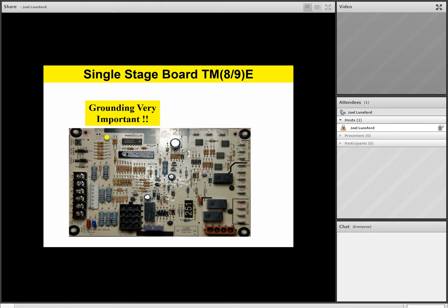You want to make sure you have a clean flame sensor. A lot of technicians have all different techniques of cleaning the flame sensor. We recommend you do not use sandcloth, but instead use something like stainless steel wool or Scotch-Brite to clean that flame sensor. If you don't have a clean flame sensor, you won't have good flame current. Check your flame current before and after you clean the flame sensor, so double check that flame current. Again, typical flame current runs between about 3.5 and 4, and for low flame current, that amber flash code will be generated at 1.5. So there's quite a range right there, but if you have a low flame current, check that grounding and clean the flame sensor.